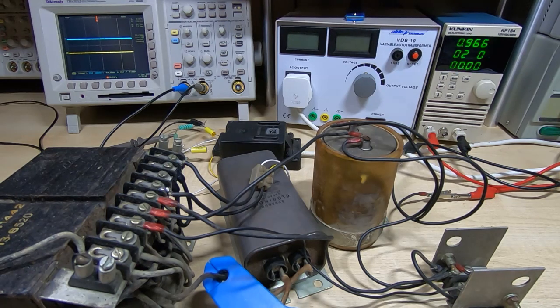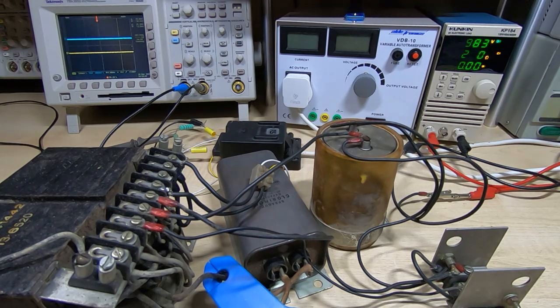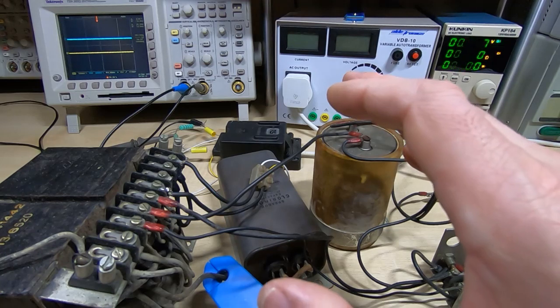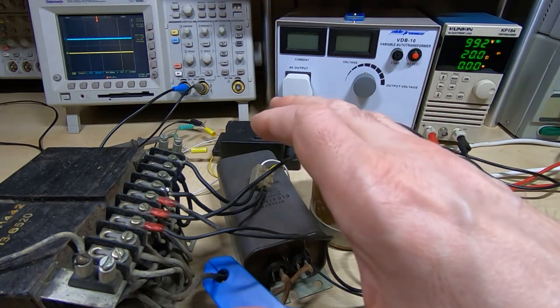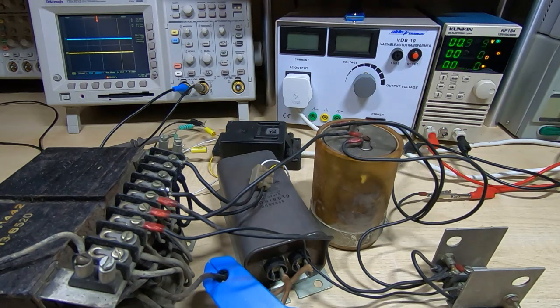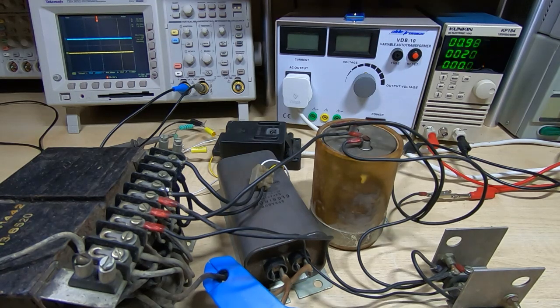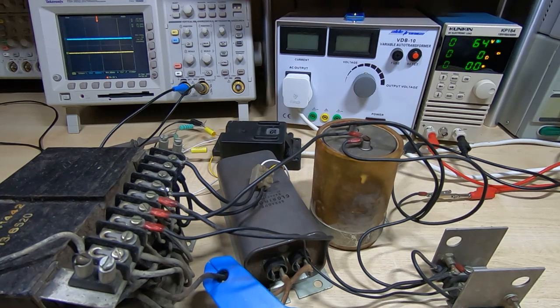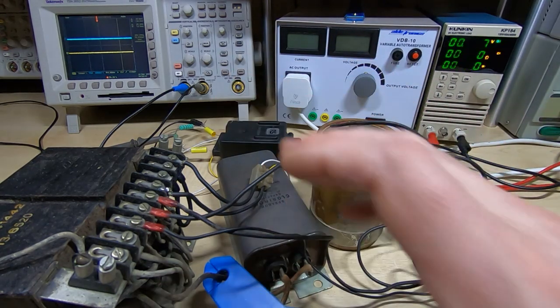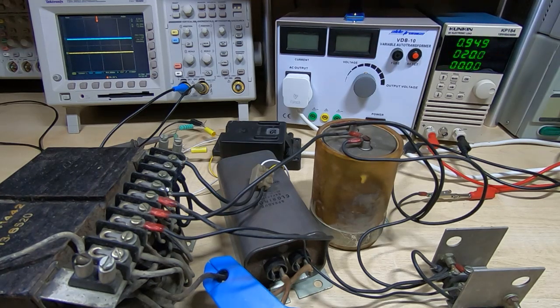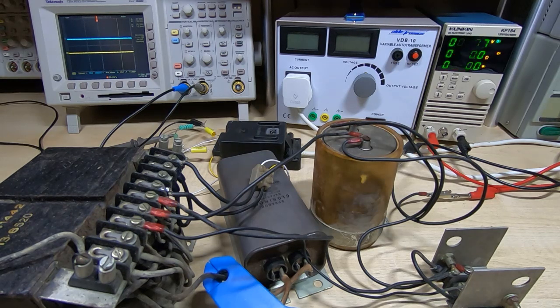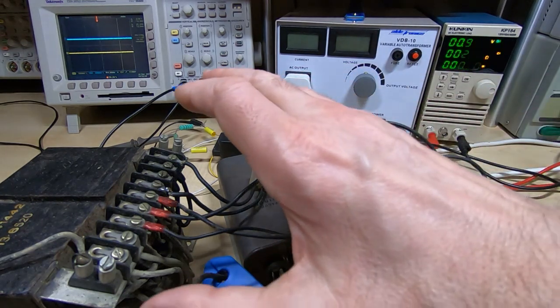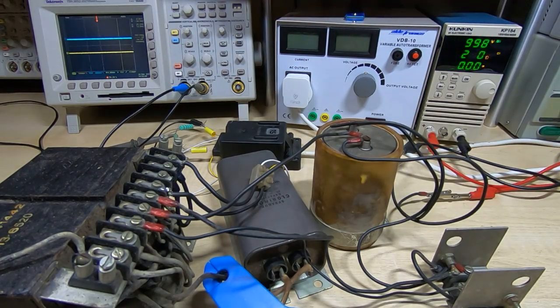OK, that's it for this video. Hopefully it's taken us a step closer to explaining how these Ferroresonant Transformers work. As I said, I've been simplifying the explanation, but I can go into as much detail as you want. It does start to get a bit complicated from here on. But in general, if you do want to use these, they're fairly simple to use. Just make sure you're operating them somewhere within their normal power rating. Usually you want to be operating them somewhere between 90 and 100% of their design rating. If you go outside of that, then they'll either be inefficient or they'll start to overheat. But having said that, they're ultra reliable. If you need a regulated supply that's going to last for 20 or 30 years without the danger of lightning strikes or over current destroying electronics, these are an ideal solution because they're pretty much indestructible if they're used within their proper operating range.